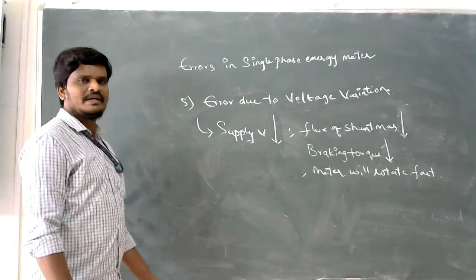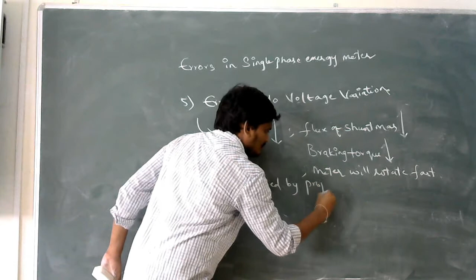This error can be compensated by the proper design of the magnetic circuit of the shunt magnet. In order to reduce the error due to the voltage variation, that is, when the voltage is very high, the meter is rotating slow. When we are having a reduced supply voltage, what happens? The meter is rotating fast.